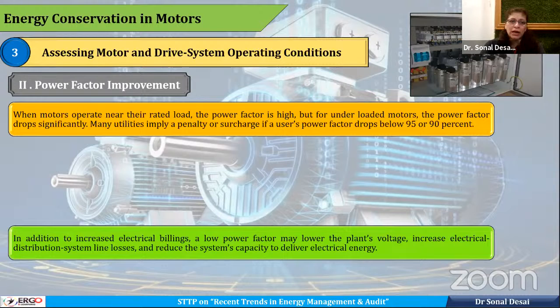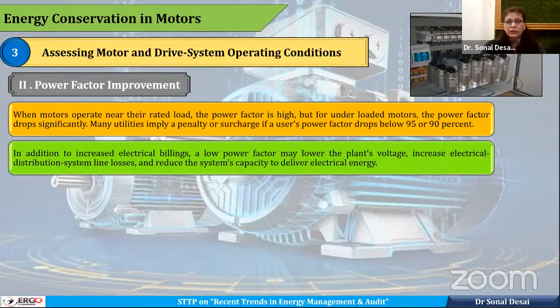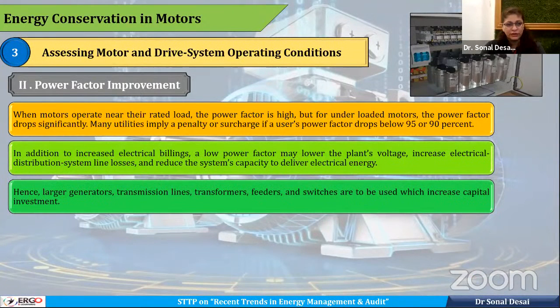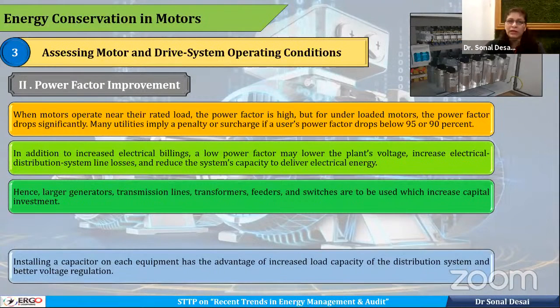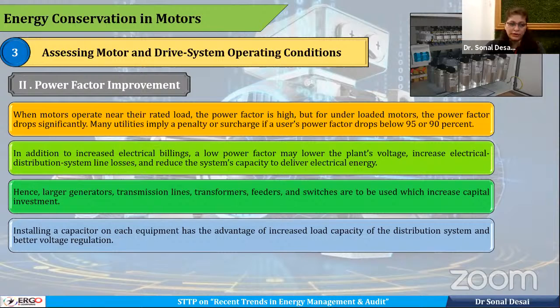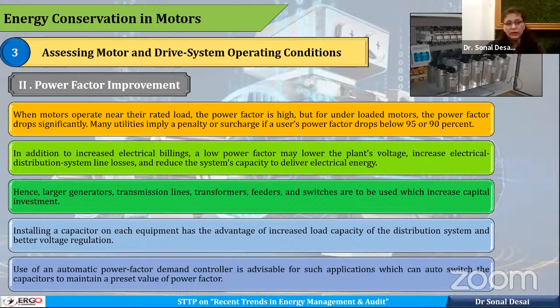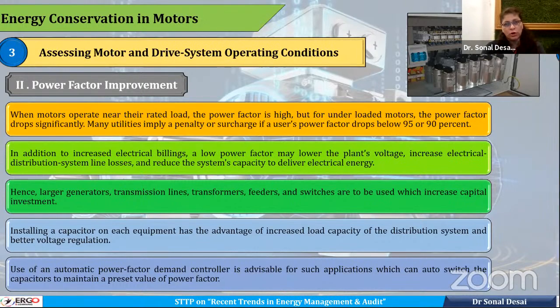So in addition to increased electrical billing with the lowering of the power factor, there will be a reduction in plant voltage. It will have an effect on the electrical distribution system and the system's capacity to deliver electrical energy, based on electrical fundamentals. So whenever transmission lines and transformer feeders are to be used, we have to select them in such a way that there is minimum effect on the power factor. Use a capacitor on almost all equipment, that will also help maintain the power factor. And use an automatic power factor controller and demand controller, because that will also help to maintain a dropped power factor.